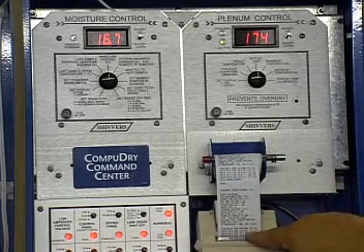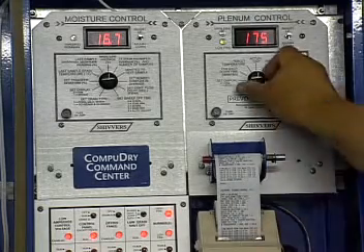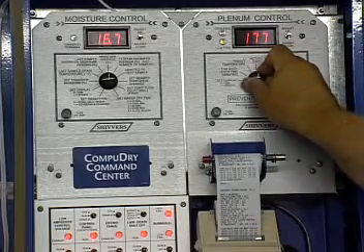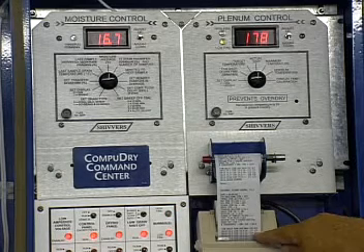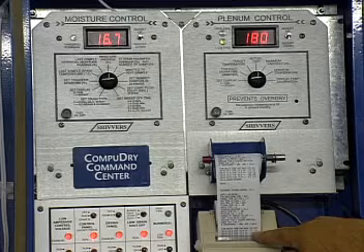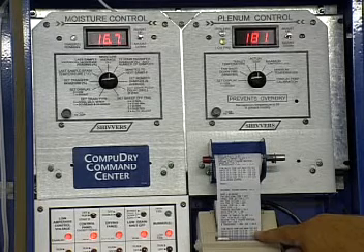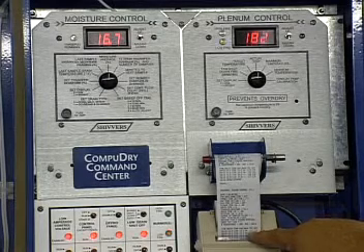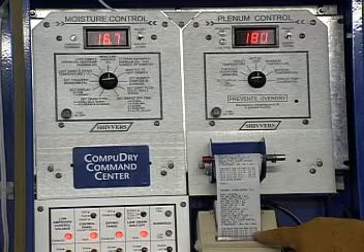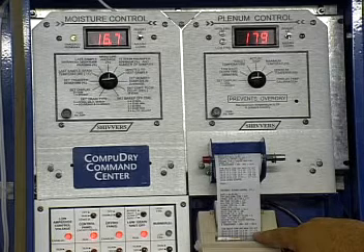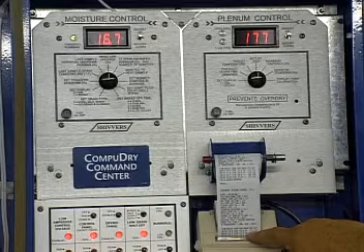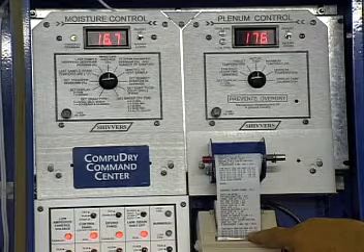The sixth column is the target temperature, which is 177, which is what it's showing down here. The actual temperature is the last column. That should be close to target temperature. If it isn't, then you need to give it a little more gas pressure. If actual temperature can never reach target temperature, you don't have enough gas pressure. If you have too much gas pressure, it's going to cycle on and off from high to low to off a whole bunch. You don't want it to do that. So you got to get your gas pressure adjusted and your vaporizer just the right temperature for correct operation.